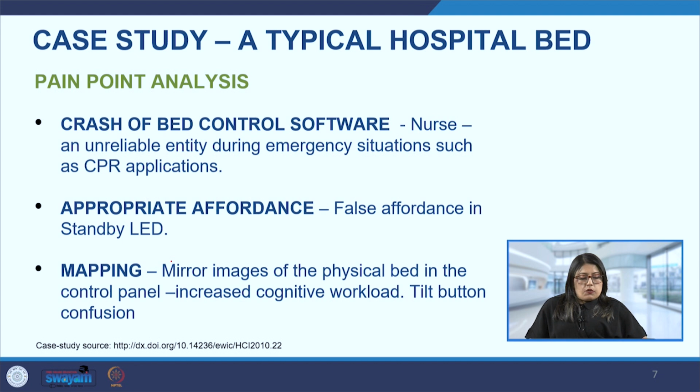The mirror images of the physical bed in the control panel increased the cognitive load. Now how should the bed be shown on the control panel? If the mirror image is placed, or if it appears as it actually looks from that position, that makes a big difference. In this case they identified that the mirror image was creating a big problem and increasing the workload, because when in the mirror we raise our right hand, we see the opposite hand being raised.